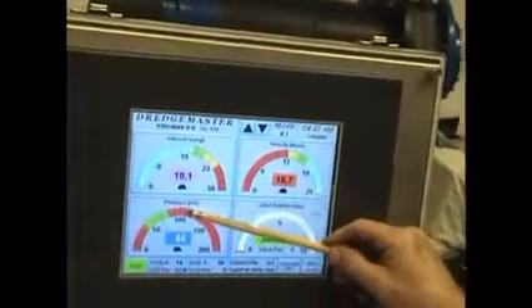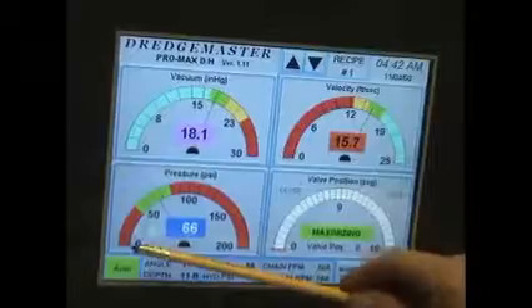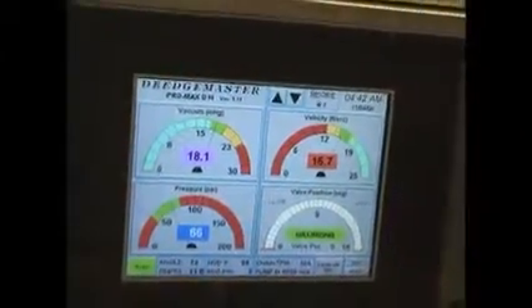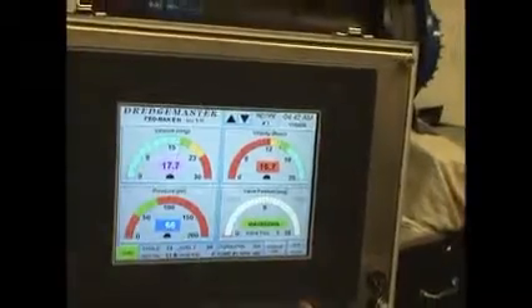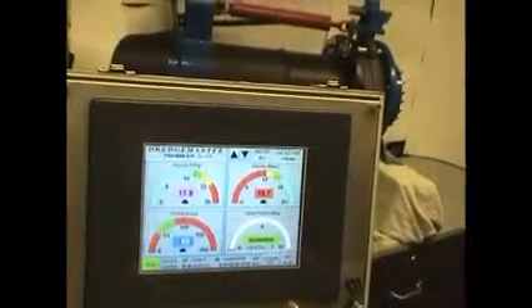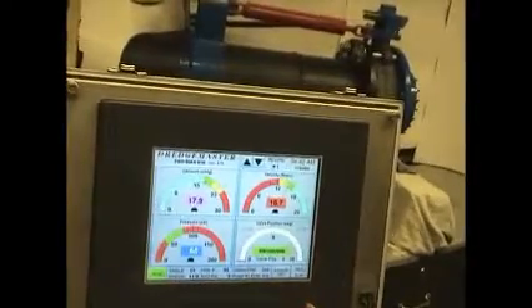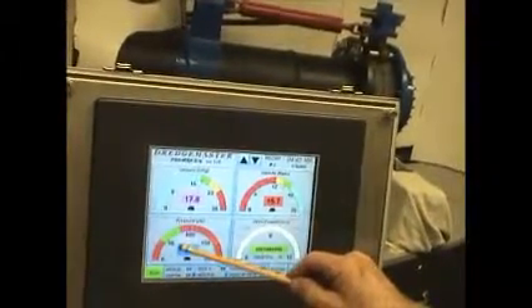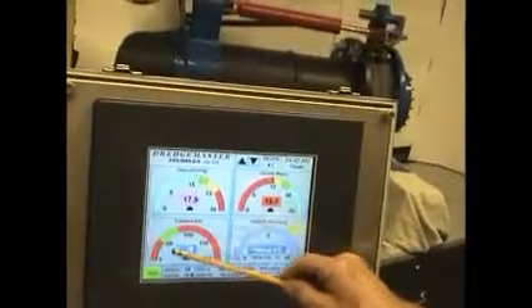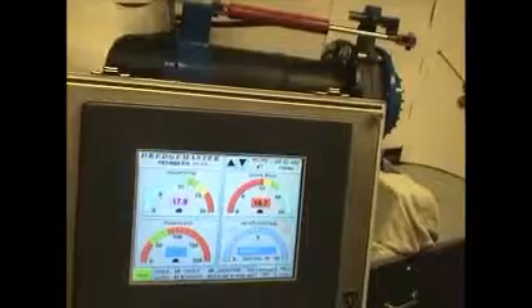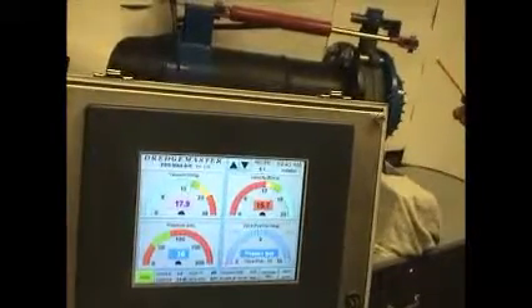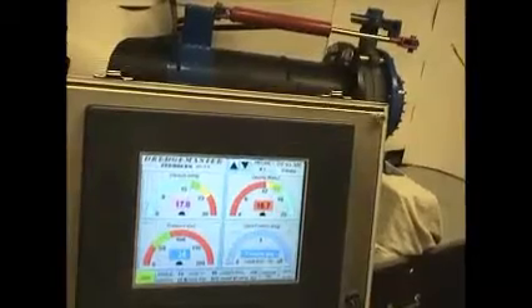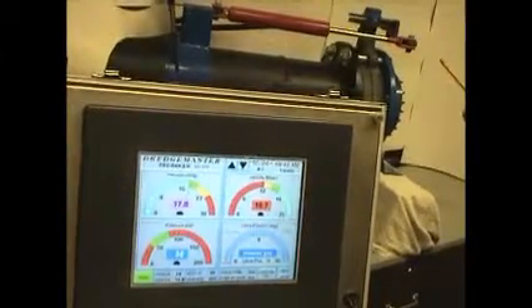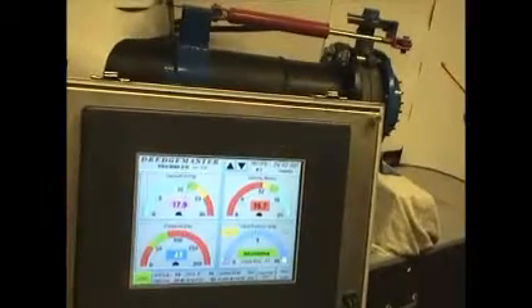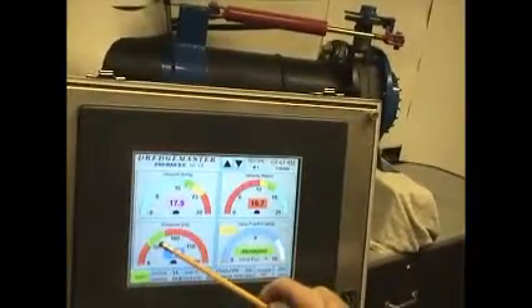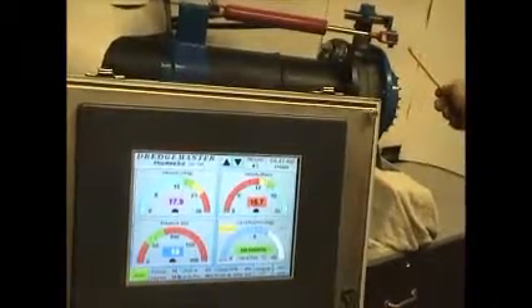The pipeline discharge pressure simply has the green area and the red areas as we described earlier. Let's simulate a condition where our pump is just about wanting to cavitate because of a heavy load in the suction side. Our discharge line pressure is dropping, got into the red zone. Our valve instantly opened up to prevent the pump from cavitating. Once we got fresh water in the suction side of the pump, our discharge line pressure is going to start to increase. Once it increases back into the green zone, we can start to close the valve back down.